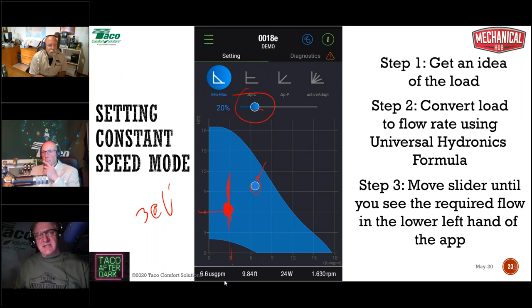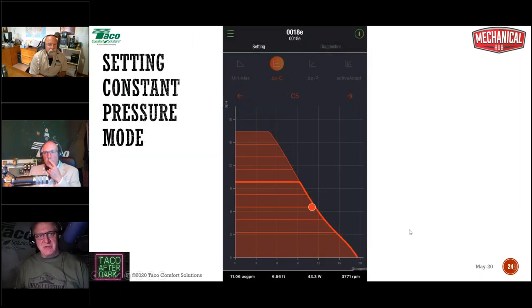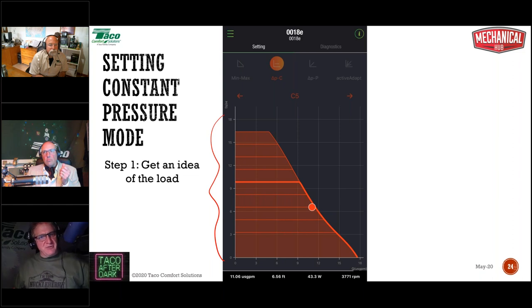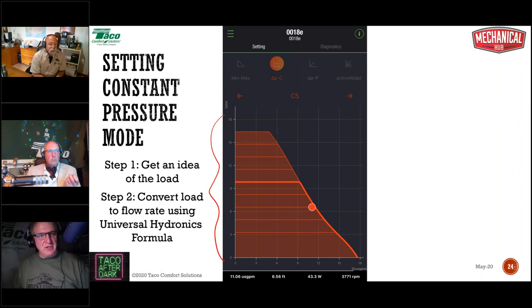Now, if we want to size this pump for a zone valve job, we can size it using the constant pressure mode. There's 9 settings here, but the steps actually go back to the fixed speed mode. So the first thing we need to do is get an idea of the total load, not zone by zone, but the total load, using the same steps that we did before. Then we convert the load to flow rate using the universal hydronic formula. So 70,000 BTUs, 70,000 divided by 10,000 is going to be 7 gallons per minute, for an example.